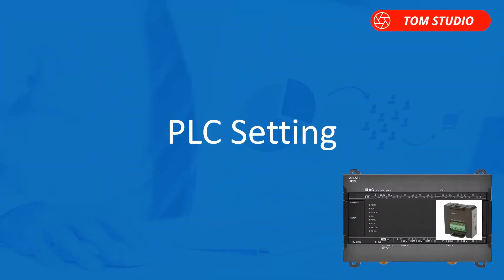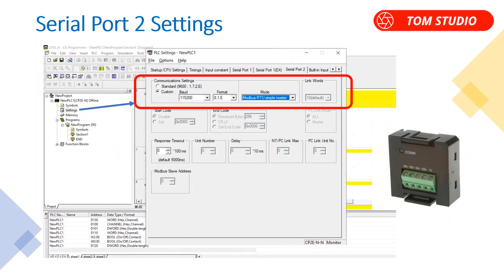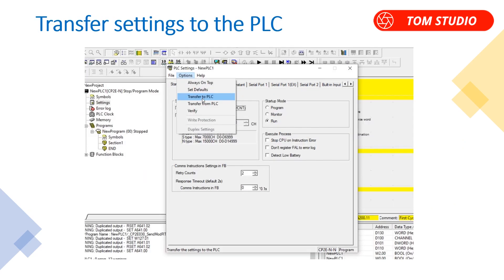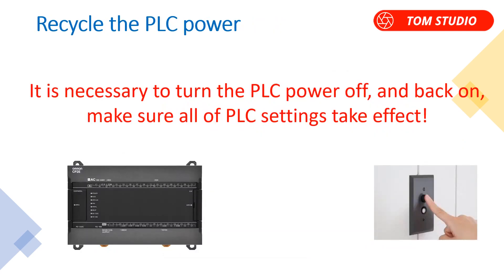Let's take a look at PLC port settings. It is necessary to configure the PLC serial communications port 2 as follows: baud rate 115.2 kbps, format 8-1-even, mode Modbus RTU simple master. Also, in the startup CPU settings, change the retry count to 2. The last step is to transfer the port 2 settings to the PLC. For CP series micro PLCs, it is always necessary to cycle the PLC power off and back on to make sure all settings take effect.